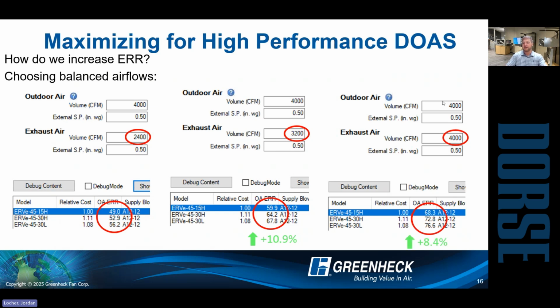So going from a heavily unbalanced system, less exhaust than supply, to a more balanced system can have significant gains in energy recovery as well, right? So I always like to preach that even a little bit extra exhaust to that unit can make a big difference in the overall performance of it. And as you can see in this example, sometimes it can be the difference between whether or not you're meeting code just by getting a little extra CFM to that unit. So trying to maintain those balanced airflows as much as possible is a way to maximize the performance of these units.